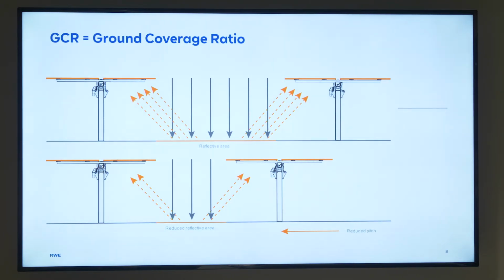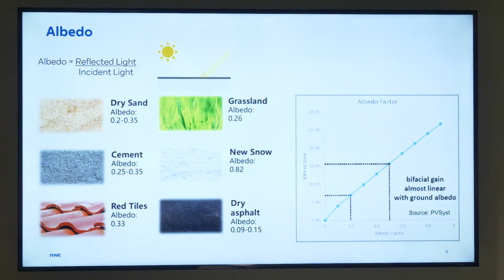Another key factor in production gains from bifacial modules is albedo, essentially the ground coverage you have underneath. In certain instances, if you can put down artificial ground covering, which isn't always applicable, you can see higher albedo gains. Traditionally what we have underneath modules is usually dry sand if we're out in the desert of Texas, or in other locations where we have to seed for erosion control, it's grassland.